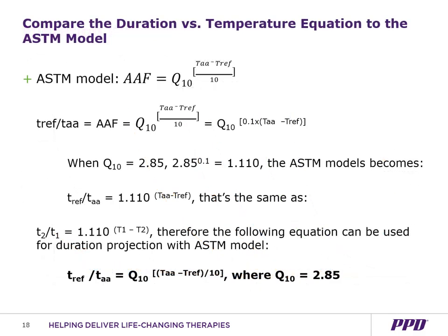We then put this into the ASTM model to back calculate the Q10 value. For stopper extracted BHT, this was 2.85. This suggests again that the ASTM model is an appropriate model for calculating the accelerated aging time when a suitable Q10 value is used.